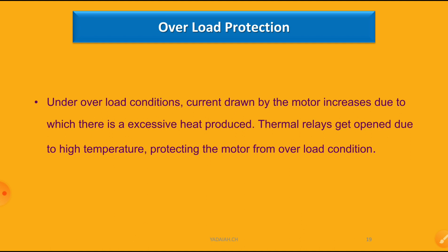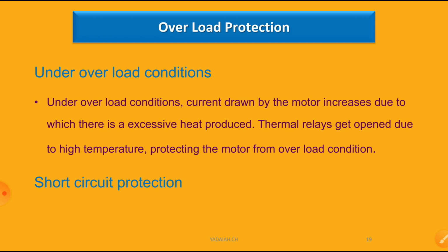Under overload conditions, the current drawn by the motor increases, due to which excessive heat is produced. The thermal relays get opened due to high temperature, protecting the motor from overload conditions. Now, under short circuit conditions, the fuses are provided for short circuit protection.